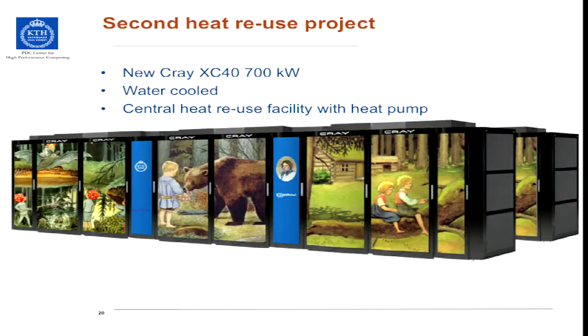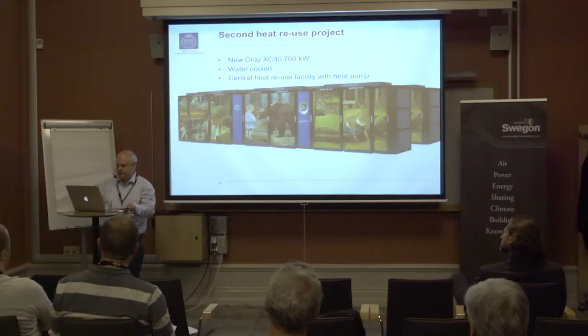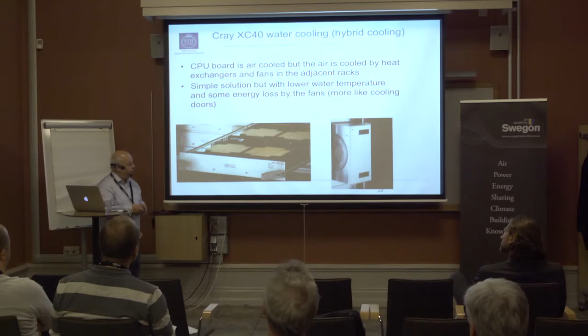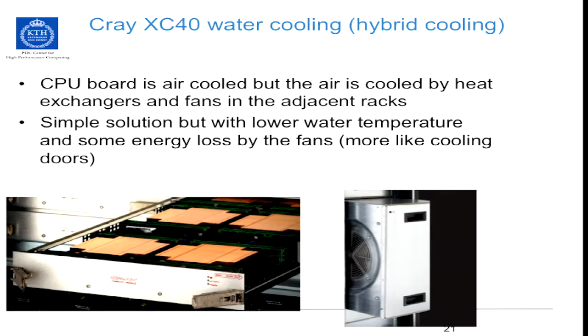But now Cray has also done a decent job with the liquid cooling system, so we could buy a ready-made system out of the box, which is very nice — we didn't have to adapt it ourselves anymore. The Cray XC40 has a sort of hybrid cooling: the actual CPU boards are cooled by air, but each rack has a built-in heat exchanger, and you also have special fan racks, or blower racks as they call them, between the CPU cabinets.